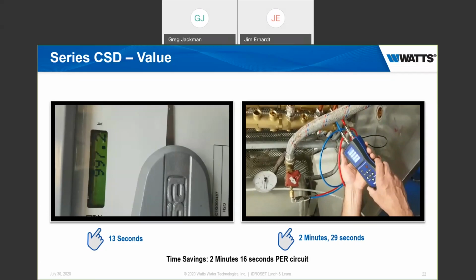Now, if you think about that, if you only have 1 or 2 valves in the system, not a big deal. But think about that system that we had on the previous slide where we had 4 stacks, each with 5 radiators. So there's 20 circuit setters there, and then we have one at the bottom of each stack, 24 of them, right? We're going to have to go through multiple times and recalibrate these. If we have to hook up a manometer every single time, even if you have 2 guys on a job, the amount of time taken to do that is amazing. It is an extremely long process, and this is the key advantage of the iDROSET, that it speeds up that part of the balancing process tremendously. And this is where the value is for the balancing contractor.